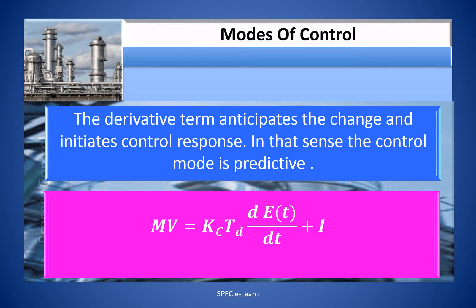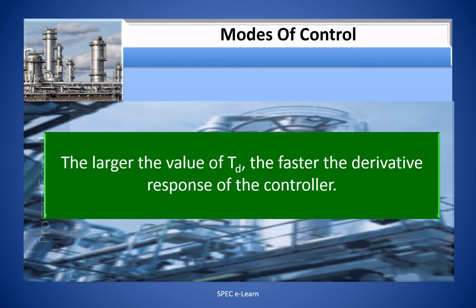The MV or output of a derivative control mode is expressed as: MV = Kc × Td × (dE/dt) + i, where Td is the derivative or rate time. The larger the value of Td, the faster the derivative response of the controller.